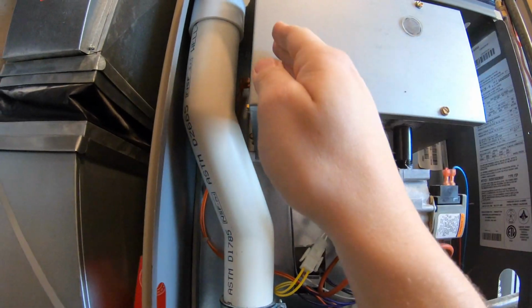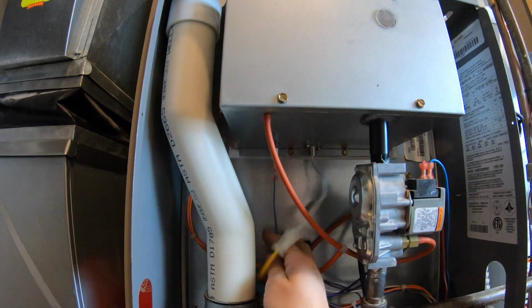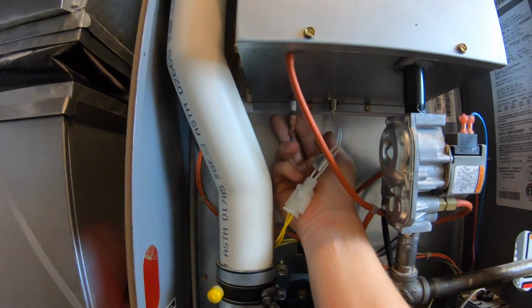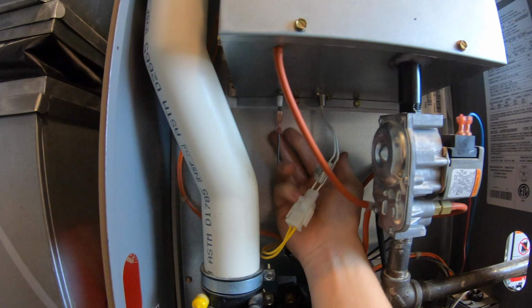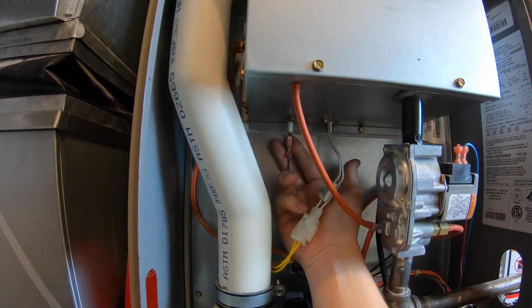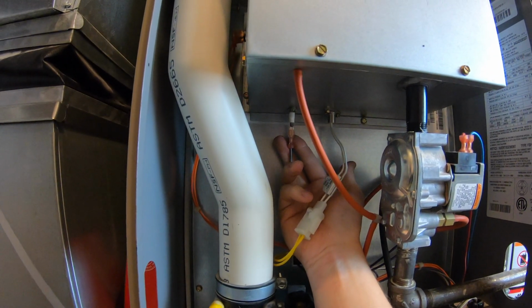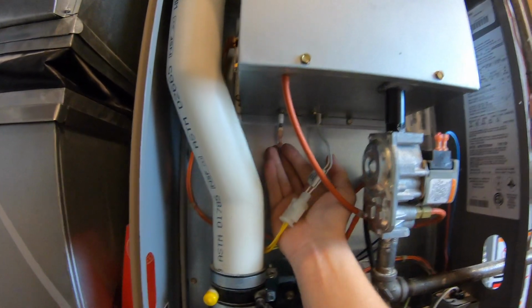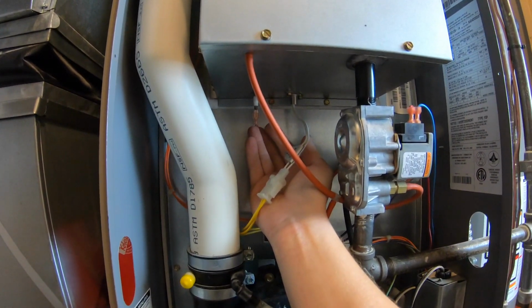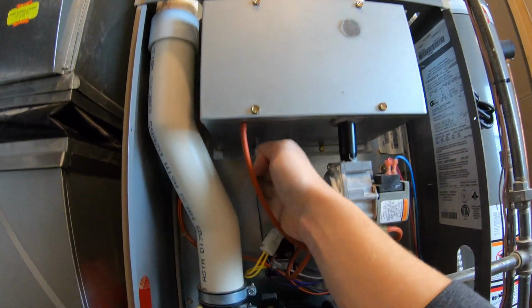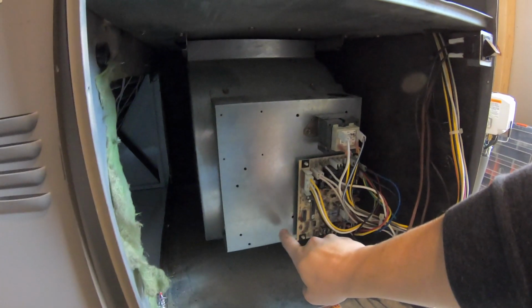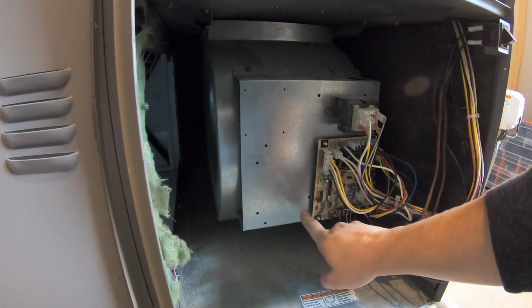Once those burners light, your circuit board is going to send power to this guy right here. This is called your flame sensor. That flame sensor is going to sense that there is a flame signal there. It's going to rectify that signal and tell the board, yep, the burners are lit. Start the blower timer. So as soon as it rectifies that flame signal, your circuit board down here is going to send power, 120 volts, to the blower motor, which is right back here. That blower motor will start to pull air and circulate it throughout the house.